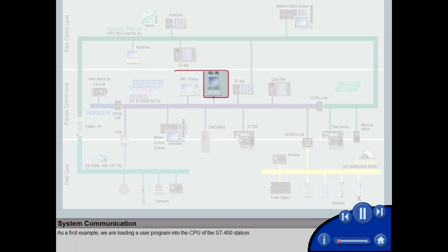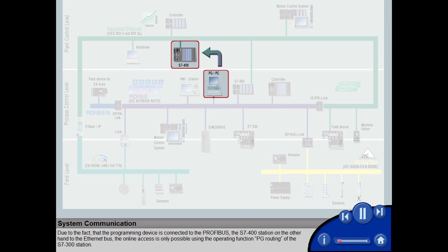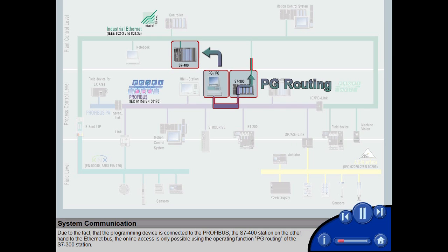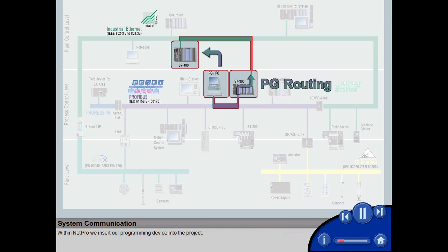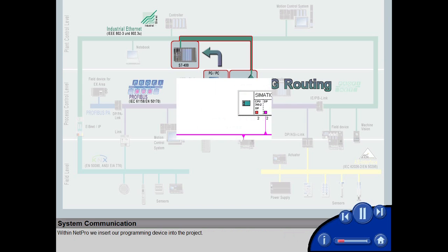As a first example, we are loading a user program into the CPU of the S7400 station. Due to the fact that the programming device is connected to the PROFIBUS, the S7400 station on the other hand to the Ethernet bus, the online access is only possible using the operating function PG Routing of the S7300 station.